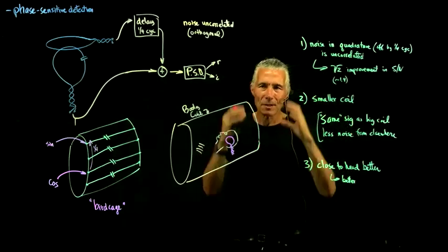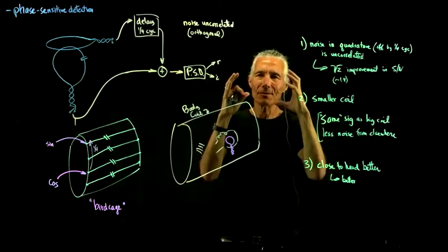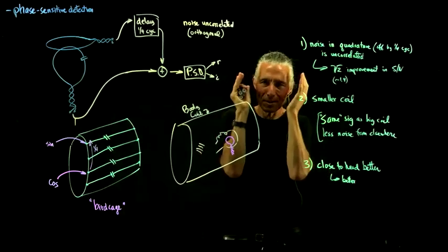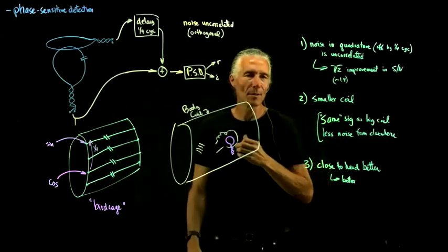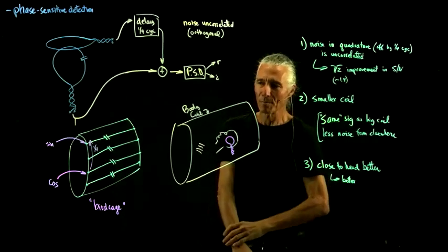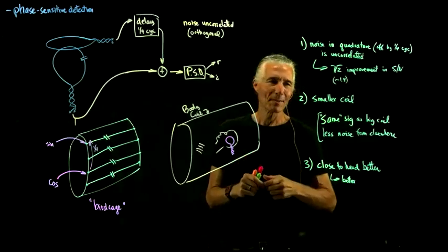And so if you could somehow make a coil that had 128 channels in it, and that was flexible, and you could move it in right on the head so that it was close to the head, you could at least double, maybe even almost triple the signal. That would be like a 6 Tesla magnet just by having a better coil.